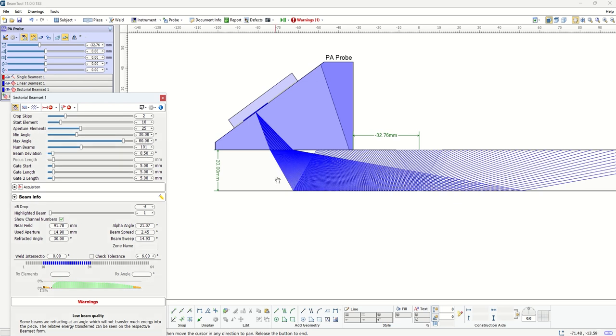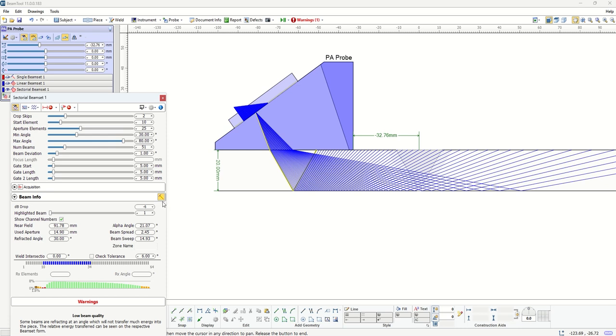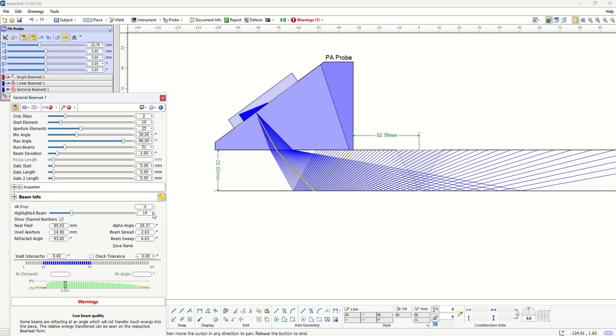Now on the beam info tab, all this information that was previously provided for a single beam is going to be available for all these beams. What we can take advantage of is this highlight tool that tells you which beam these informations are for. Right now we are on our minimum beam which is 30 degrees, so you have all these informations for refraction at 30 degrees, alpha angle inside the piece, and all other information. If you toggle this highlighted beam, you can go to any of these beams and you will see that the information here will be updated for that specific beam.